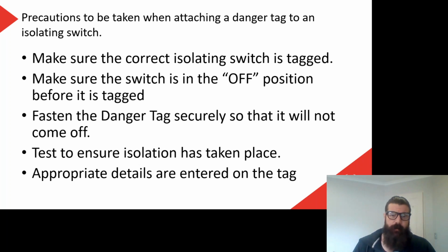So most of that is just part of our isolation procedure. But points to note there, make sure we put our danger tag on so it doesn't come off. Most of your danger tags will have a hole in it that you can put your lock through, so at the same time you lock your isolation, you attach your tag to the lock. And at the bottom there, it says appropriate details entered on the tag. So we're going to write generally who we are, and your phone number is a good idea, and perhaps the date as well. So if anyone else is coming along, if they need to turn it back on, they can get in touch with you. And it's far less likely that someone will remove a tag when they shouldn't if they can see contact details on there, because they'll go, I'll just ring the guy.